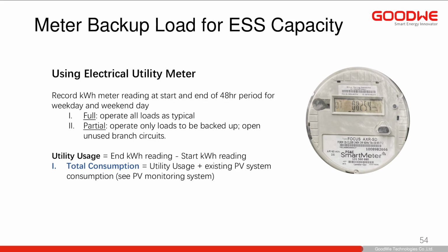Now, if you have an existing PV system, that's going to mess up that reading. You have to factor that in. So if you have a unidirectional meter, you're going to have to add in your existing consumption to that. If you have a bidirectional meter, you're going to have to add in your existing production.